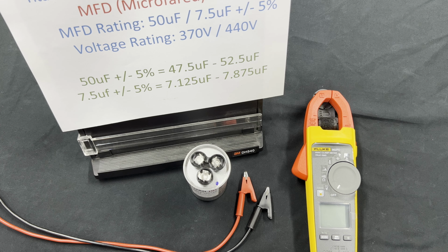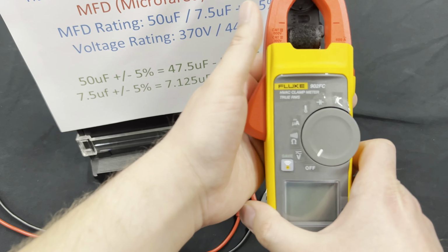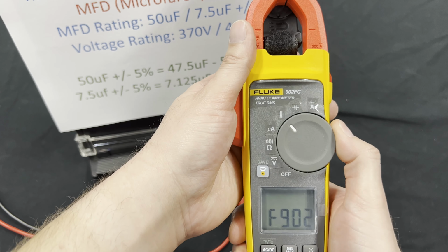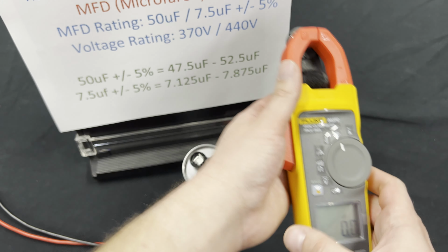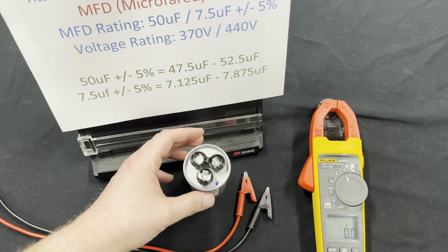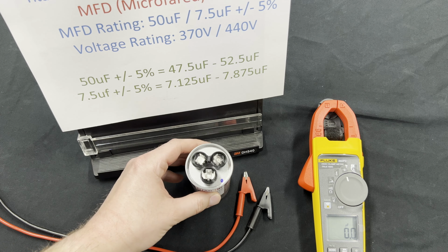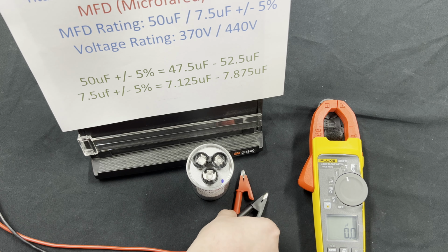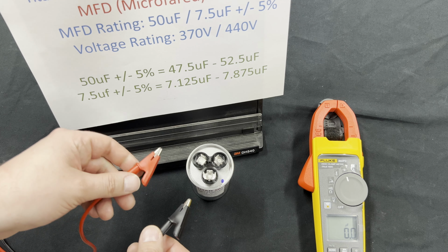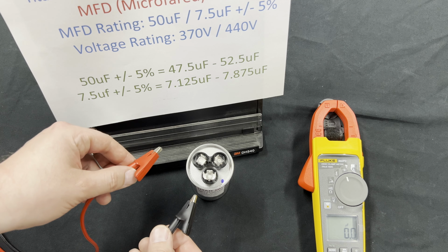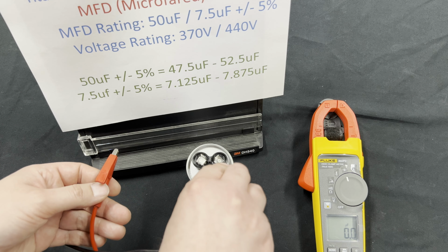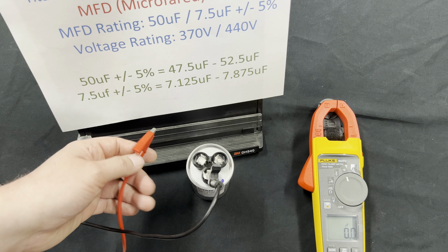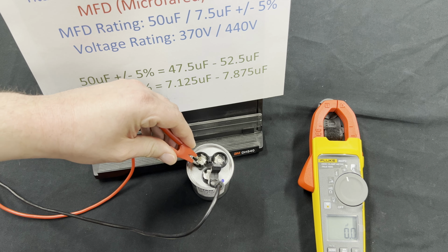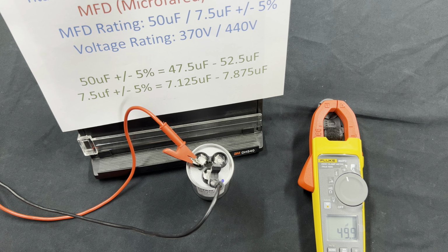For testing purposes, you'll need a capacity checker or a multimeter with a built-in capacitance setting. This Fluke 902 HVAC Clamp Meter has a built-in capacitance setting. This capacitor has already been discharged. When reading a capacitor, polarity does not make a difference. Take one probe, put it on the common. We'll take the other probe, put it on the compressor terminal.